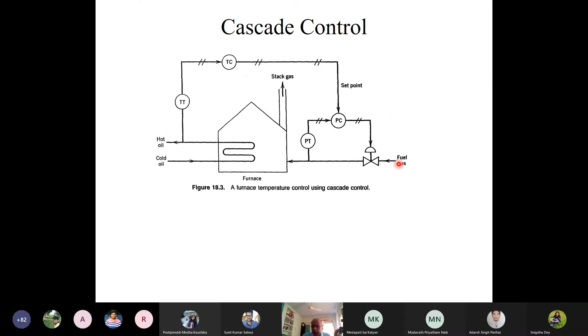That we can implement if we put a pressure controller over here. This pressure controller basically measures the pressure, this line pressure, which is basically related to the flow rate of the fuel gas. Normally when we measure the flow rate of a gas, we measure the pressure, which is related to the flow rate. So we measure the pressure over here, and we have a pressure controller. Based on the pressure over here, we open or close the control valve. And this pressure will fluctuate as the header pressure fluctuates. So the controller will see that pressure and immediately take corrective action by changing the opening of the control valve. Okay, so here you can see we have one output and one manipulated variable, but you are using two controllers over here.